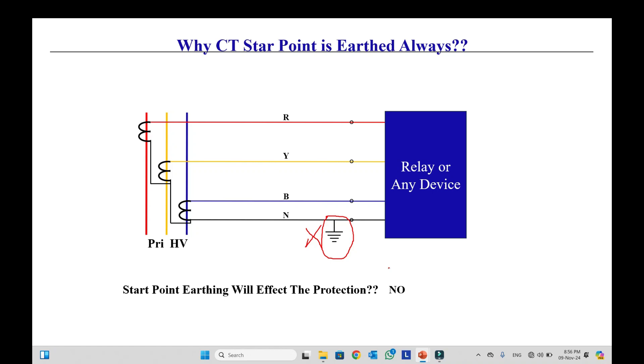Why? Because the earth is not connected to the star point for the metering or measuring device internal function. There is no role of earth for this, because the circuit without earth is complete. We have red phase, yellow phase, blue phase. It will go to the device and neutral will also go to the device and it will be connected internally. So circuit is from CT to the device. Circuit is complete without the earth. So the question is still remaining, why do we need earth?